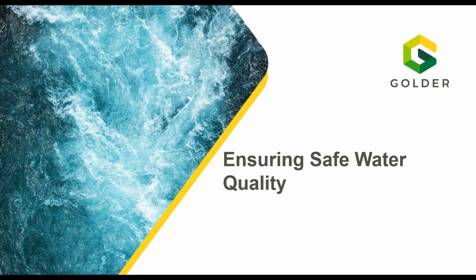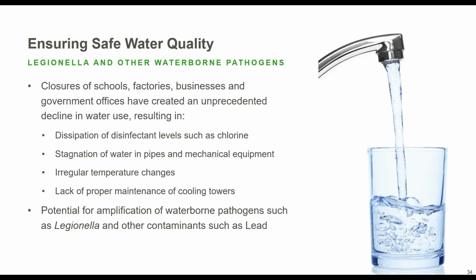So as Dave mentioned, the other major concern as far as potential hazards associated with buildings is related to water quality. Closures of many buildings have created an unprecedented decline in water use. This in turn may have resulted in dissipation of disinfectants, such as chlorine, stagnation in water pipes and other mechanical equipment, such as hot water tanks, irregular temperature changes, especially in warmer climates where potable water systems may be sitting at room temperatures, which can promote microbial growth, and lack of proper maintenance of cooling towers and any other water features if present. Also spas, whirlpools, etc., while not in use or being properly maintained, may have to be taken out of service and completely drained.